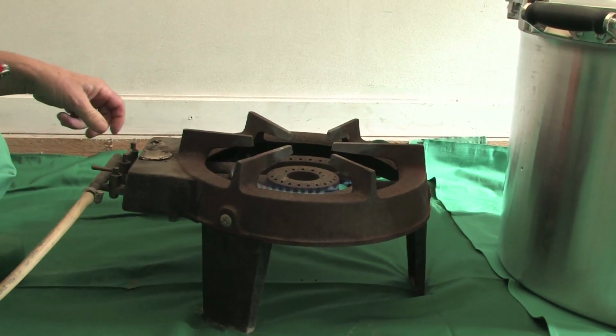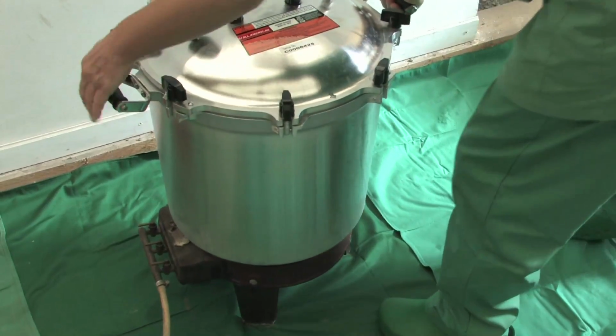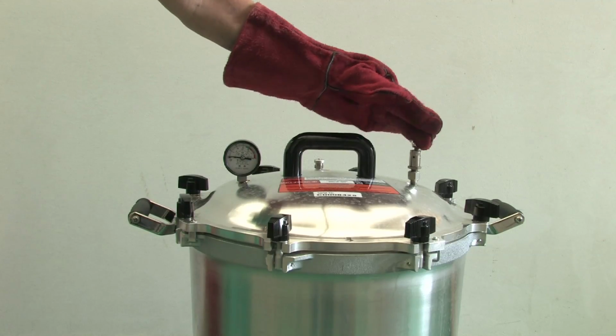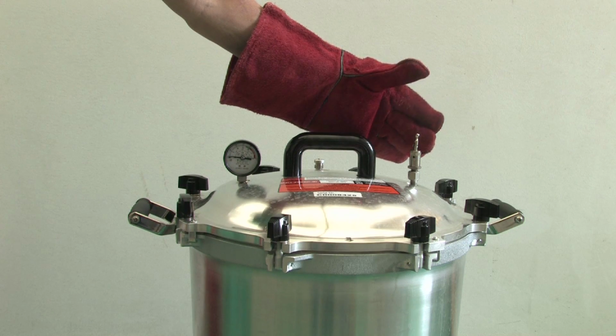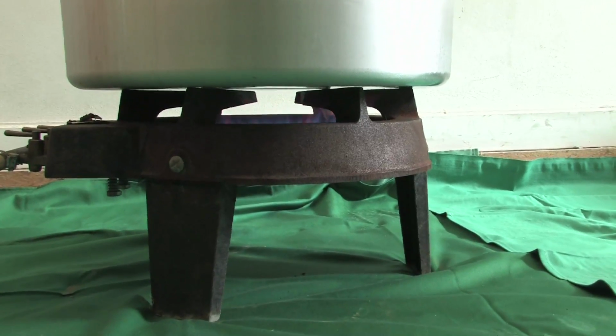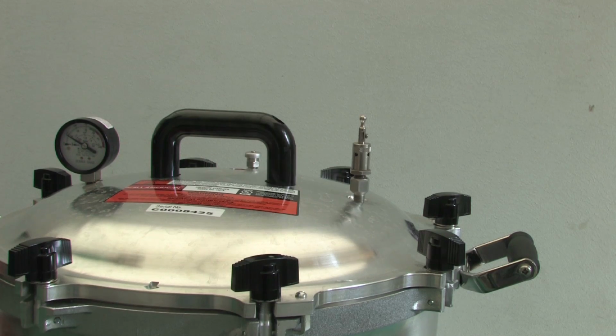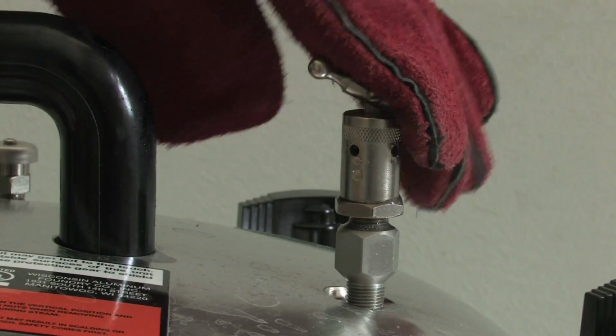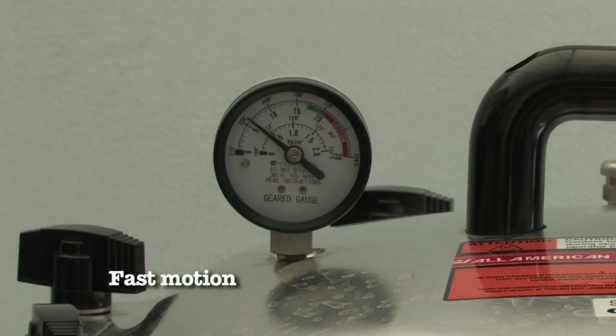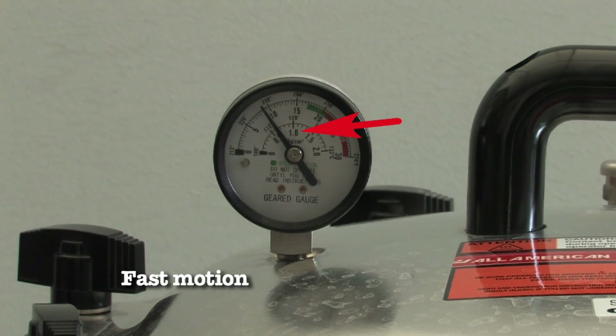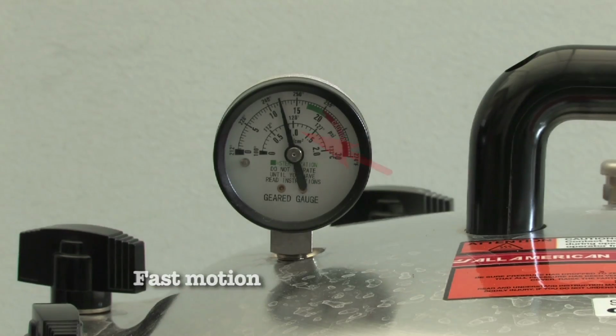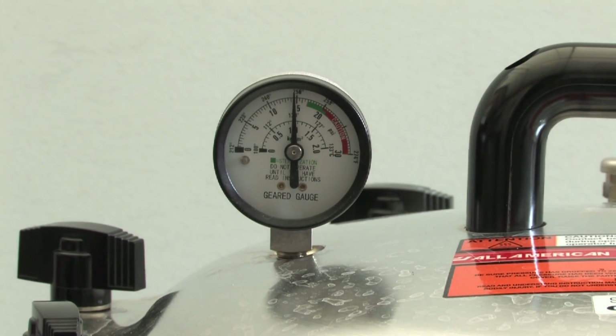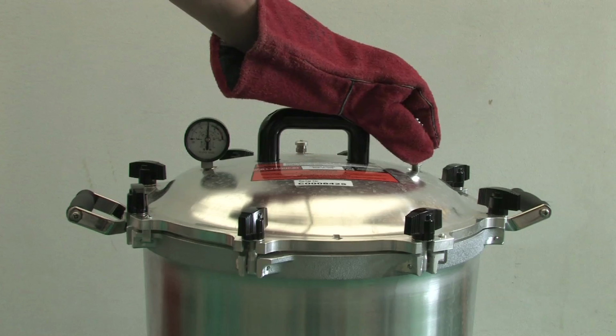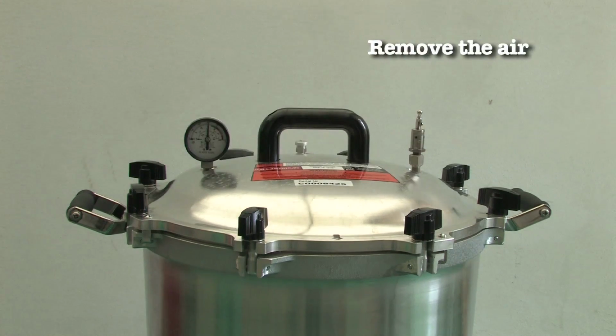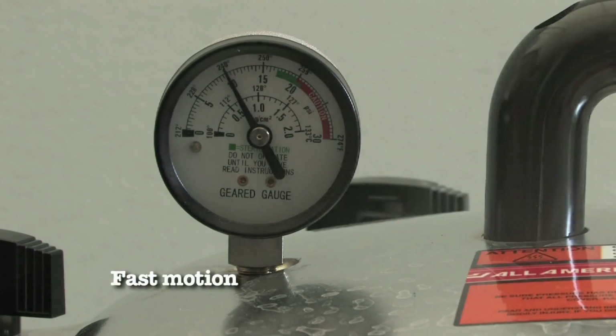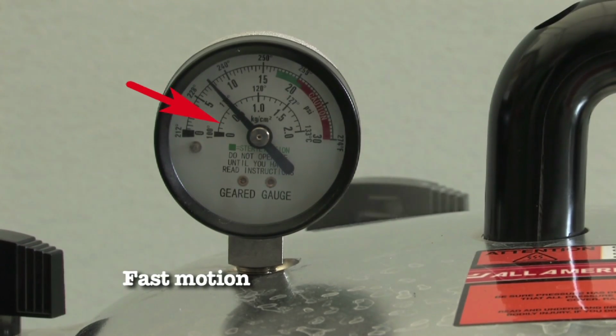6. Place the autoclave onto the heat source. 7. Open the purge valve, vertical position, and turn heat to high. 8. When a continuous jet of steam escapes from the purge valve, close the valve. Allow the pressure to rise to 1 bar on the pressure gauge. Then, open the purge valve to allow air out of the autoclave. Let the pressure drop to 0.2 bars.